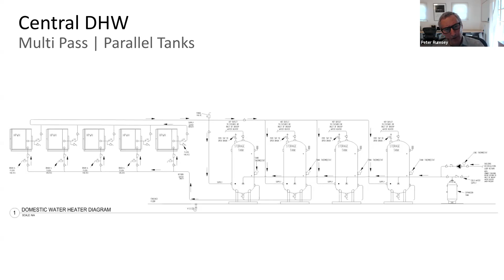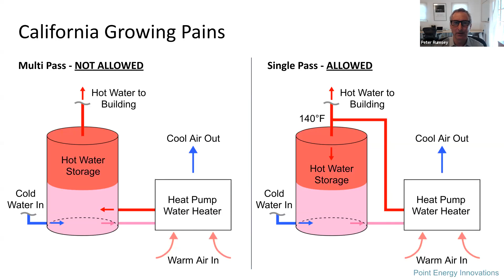There's a weird thing happening in California that came up a couple weeks ago when we were talking about domestic hot water. The California Energy Code, Title 24 for commercial buildings, until very recently was not allowing heat pump water heating in any form, and we'd have to get exceptions each time we wanted to use a heat pump for water heating. They've now written a letter allowing the single-pass system, a heat pump that takes cold water in and raises it all the way up to 140 degrees directly, sending it right into the building. They don't allow the multi-pass system, even though those can be just as efficient as the single-pass. It's just a misunderstanding at the state level. The next version of Title 24, coming out in 2-3 years, will hopefully get this fixed. There are still growing pains in understanding how to apply heat pumps in buildings, and hopefully that'll get smoothed out.